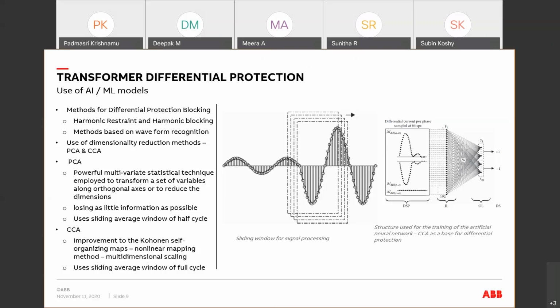When we are using these algorithms, the goal of the algorithm is first to reduce the dimensionality of the high dimensional data space formed by the differential currents to find the projections resembling the characteristics of the original space. Basically, we are talking about the differential currents, I differential between A and B phases, I differential between B and C phases, I differential between C and A phases. So in a three-phase system we have three currents, and at the sampling rate that we are talking about, a huge amount of data. So basically what the PCA does is it reduces the dimensionality. Say for example, they use the modal analysis, neural networks are used for the pre-processing both in PCA and CCA case.